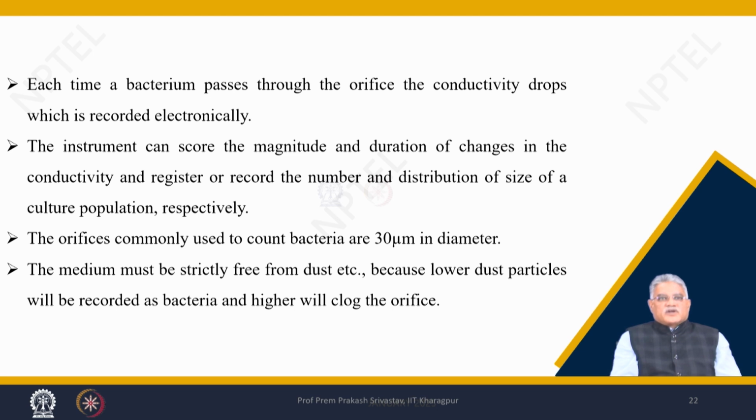The orifices commonly used to count bacteria are 30 micrometer in diameter. The medium must be strictly free from dust, etc., because lower dust particles will be recorded as bacteria and higher ones will clog the orifice.